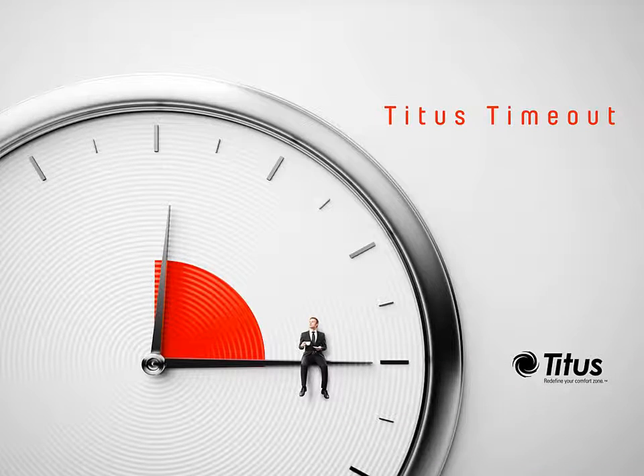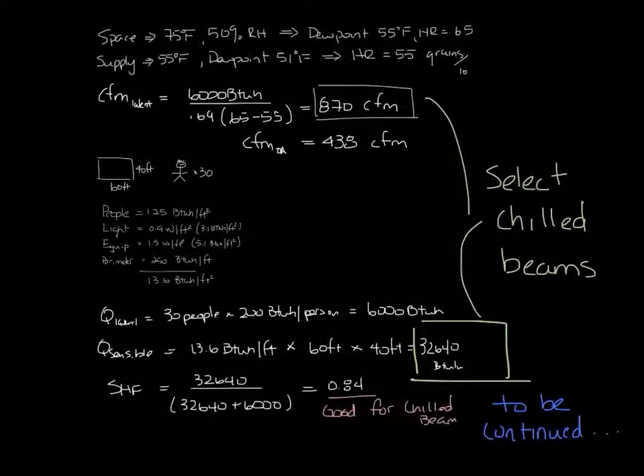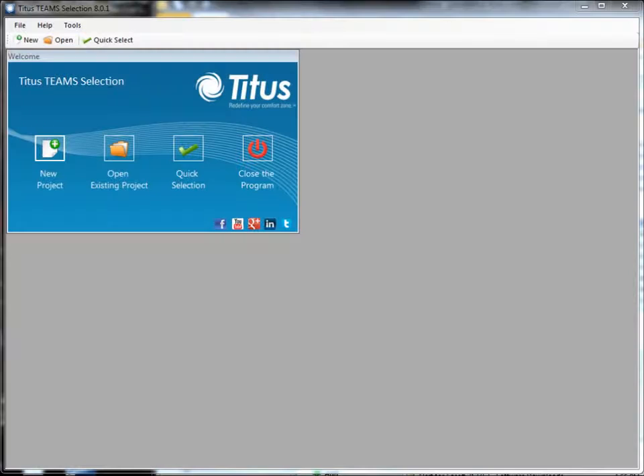I'm Jenny Abney-Civy, and this week we're going to pick up where we left off last week, and we're going to select chilled beams. Last week we left you hanging with this 60 by 40 space with 30 people, 870 CFM, and 32,640 BTU of sensible load. So now let's open the selection program and actually select the beams for this space.